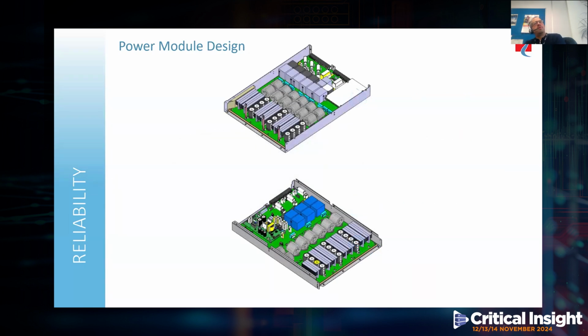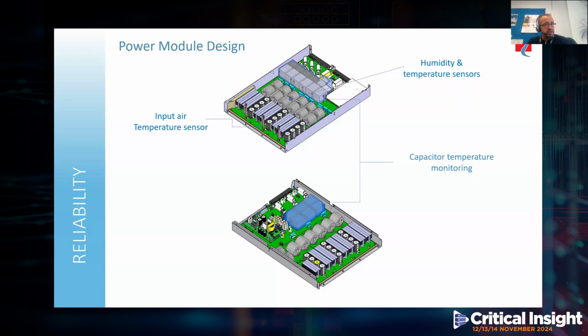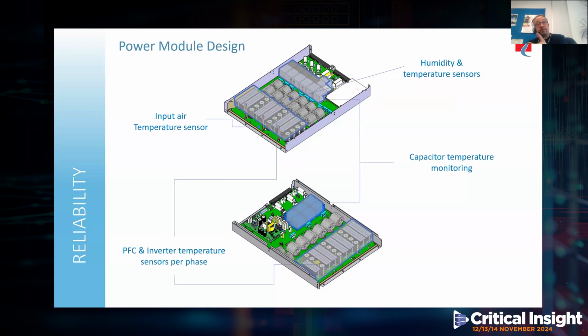Now, in developing the module, we've even considered the environment. Each module is provided with humidity and temperature sensing. They have input air temperature monitoring. They have capacitor temperature monitoring. They have PFC and inverter temperature sensors per phase. Basically, the module builds a full environmental and thermal map for monitoring and full predictive maintenance.